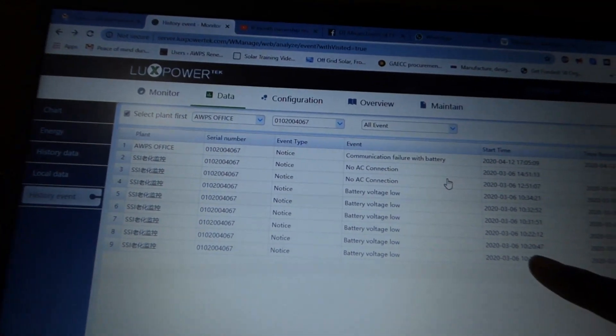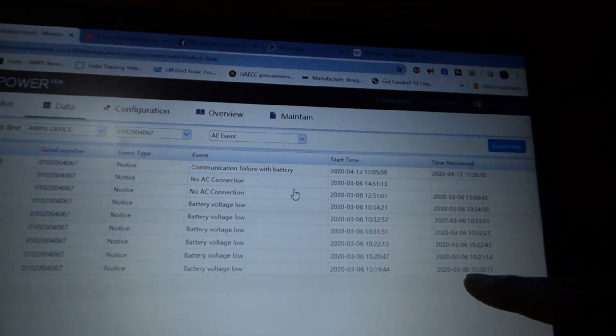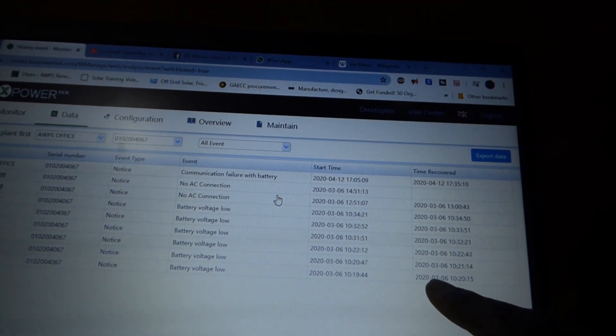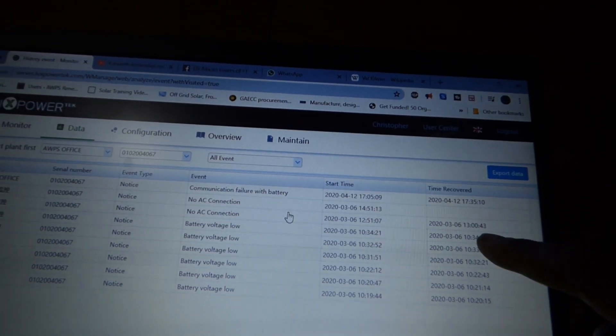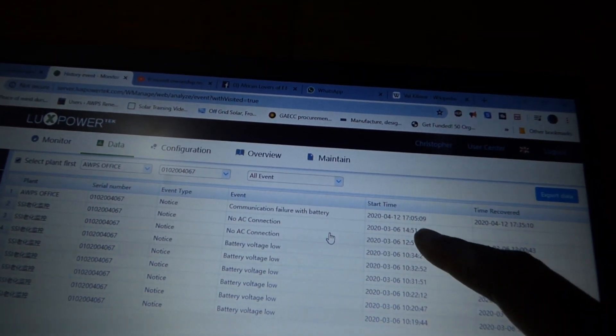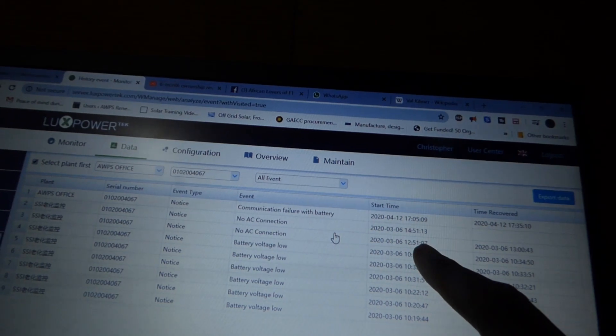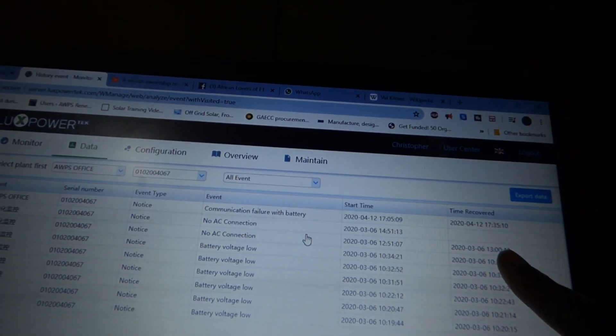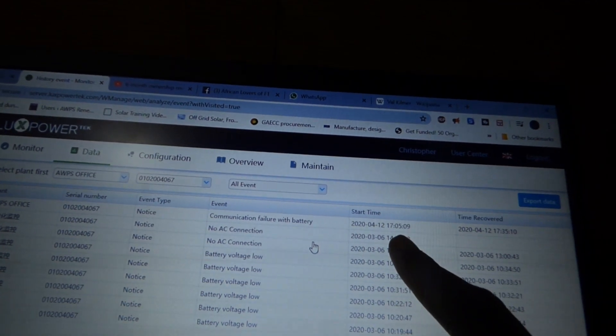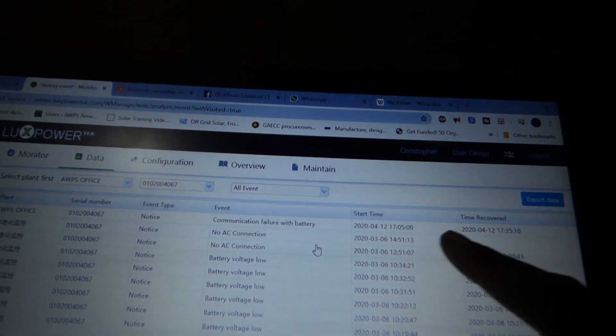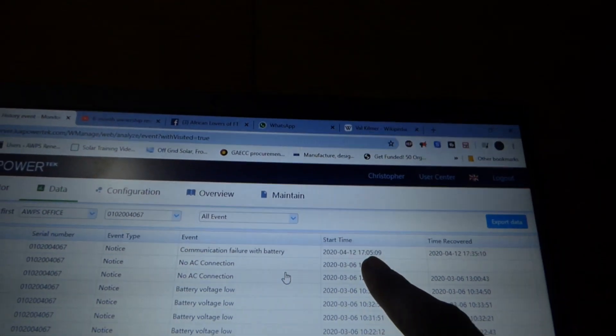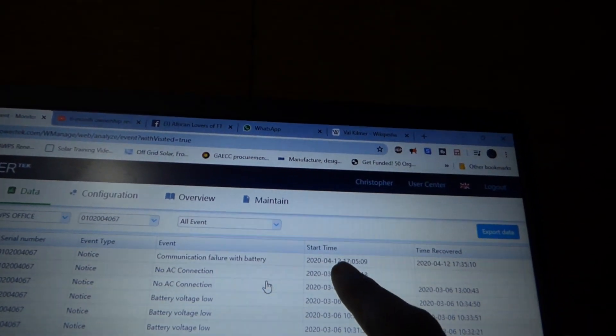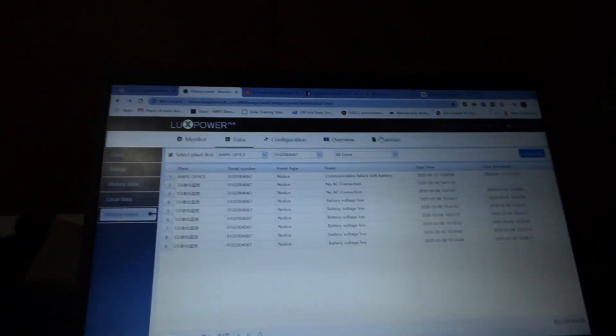And now it shows you all the messages they had. So I guess this was when they were testing it in the factory. You notice the event all occurred about the same time—March 6th. At 1020, 1021, all the way 1034. And then at one o'clock, it said no AC connection. And then at 1451. So this was 1251. The start time 1251. And then one o'clock, no AC connection. And then the same error started again. I guess they switched off before it could recover. And then here my error showed—communication failure with battery because it was showing lithium ion battery. 1705 and by 1735 that error had corrected itself.